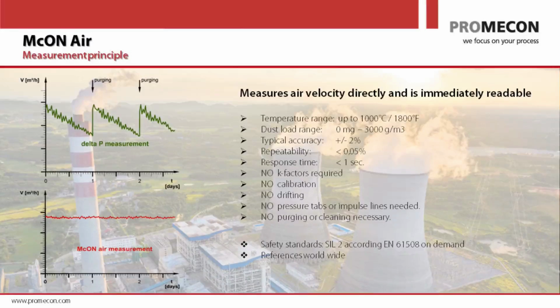And think about how many measurements you have in your plant. You have 20 measurements, 30 measurements, a lot. And none of these measurements will you ever have to recheck. One other thing that people frequently have to recalibrate for is zero, right? If you have a delta P measurement, your membrane needs to be zeroed correctly. Now, for our measurement, zero doesn't exist, as you can see.